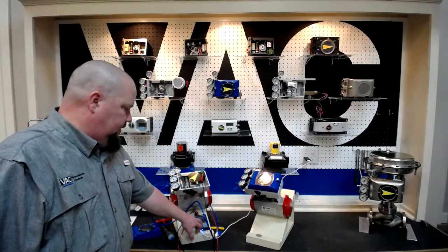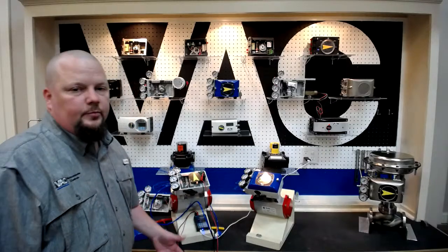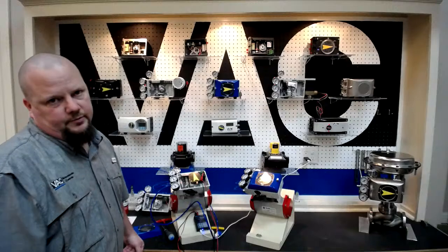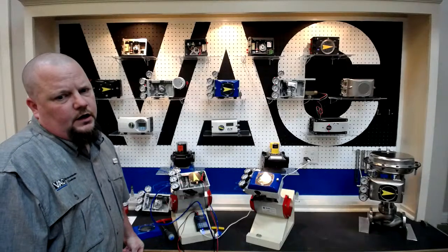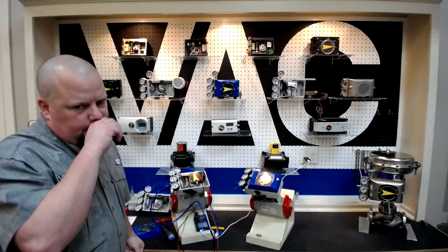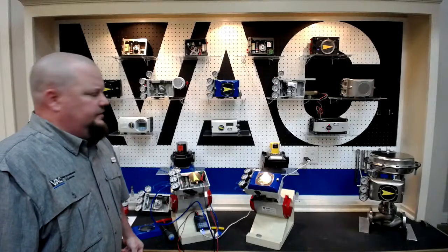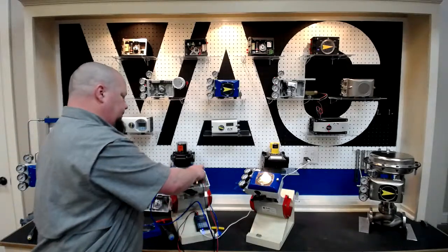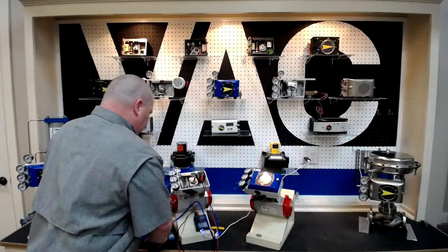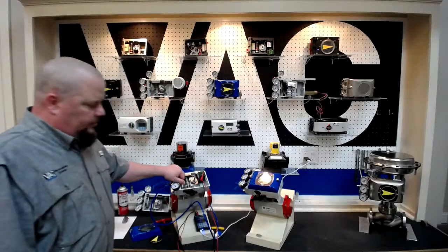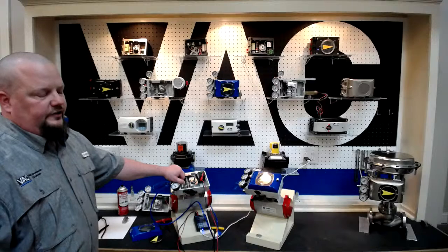Now as we ramp it up, we see that it's operating properly. So it was a simple cam setup issue. Another issue that we see oftentimes is that the cam is loose. When the cam is loose, this is another part of the operation that is undesired operation.